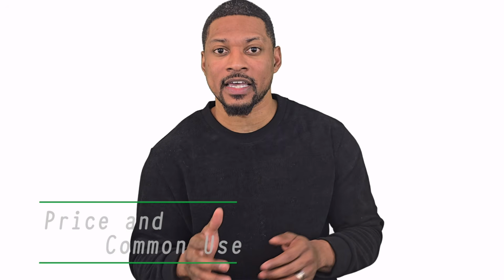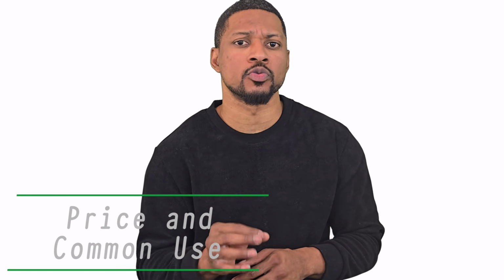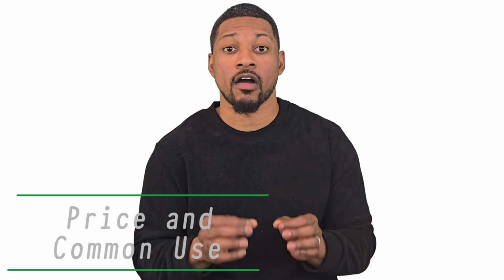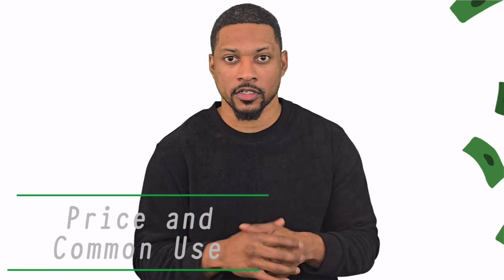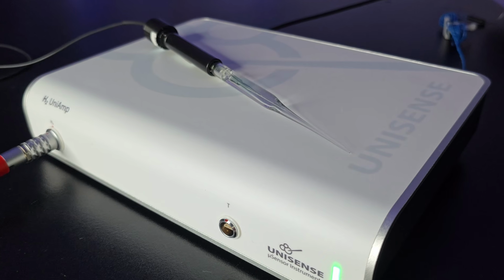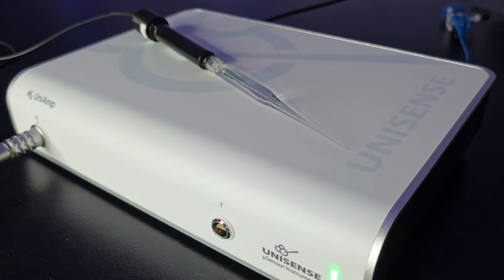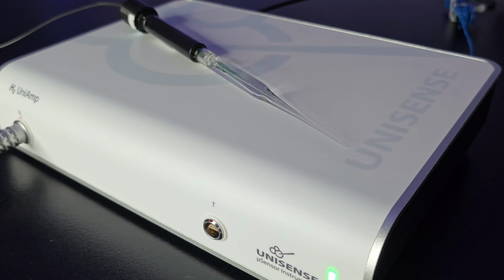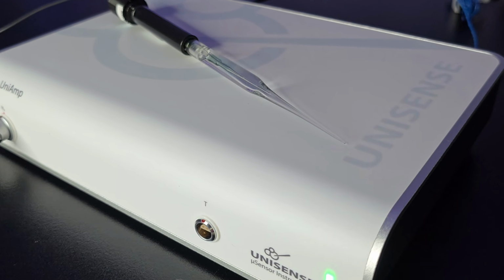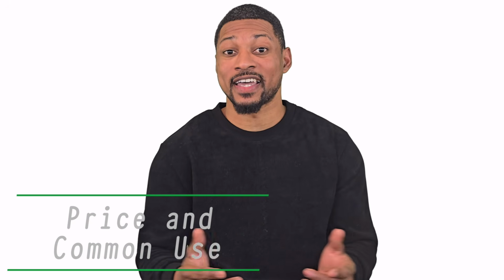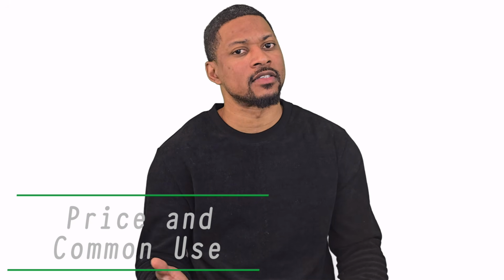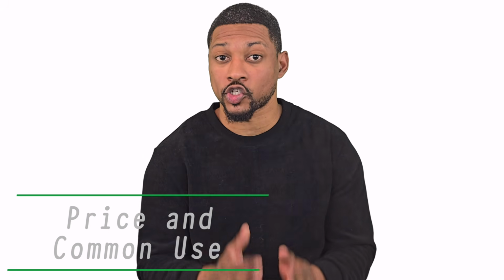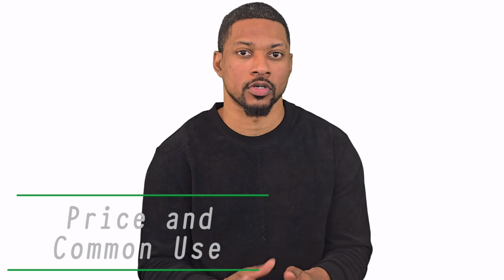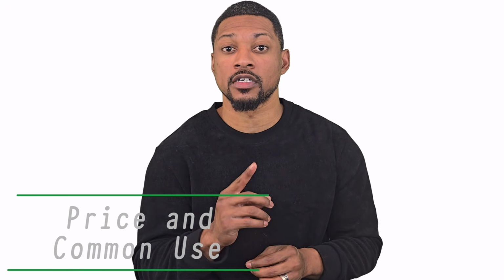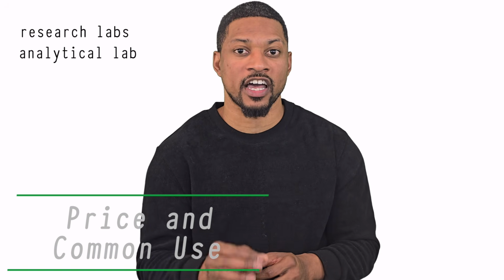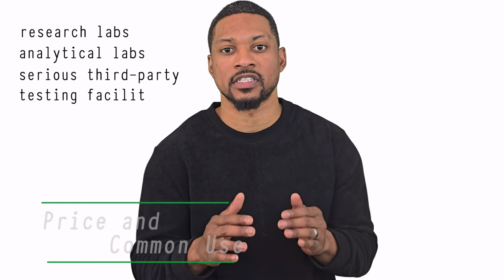This is a high-end laboratory instrument, not a consumer toy. The complete setup can cost up to tens of thousands of dollars. The Unisense hydrogen sensor alone can cost thousands of dollars. Additionally, the sensors have a limited lifespan and require ongoing replacement over time. This is why it's a laboratory tool and not a consumer device. The system requires training and strict calibration protocol. As with GC, it's primarily used by research labs, analytical labs, and serious third-party testing facilities.